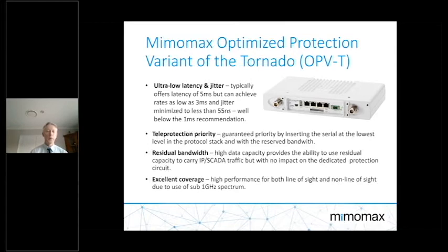We've mentioned residual bandwidth, so allowing additional bandwidth for other residual use, such as IP SCADA traffic, and that has no impact on the dedicated protection circuit. So allowing IP SCADA, we mentioned the RTU, we mentioned the VoIP, without impacting the availability or resilience of the serial protocols that are running across the radio as well.